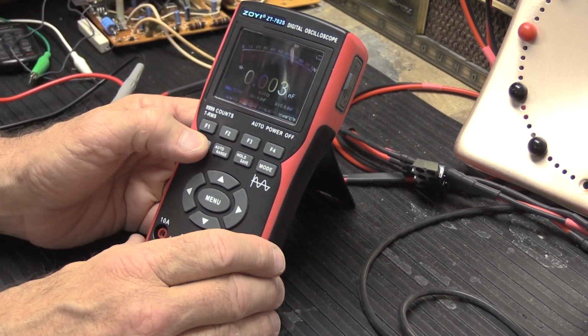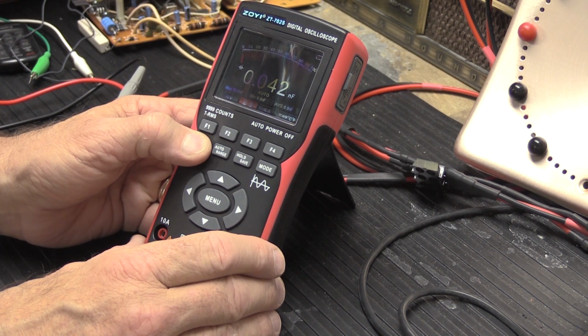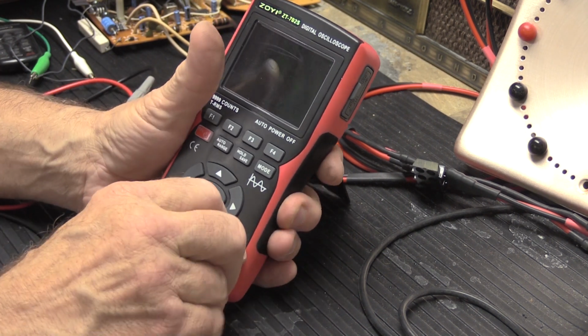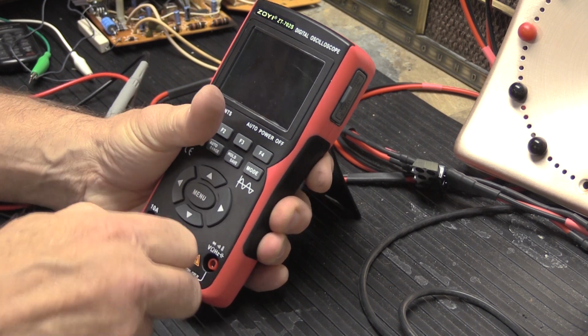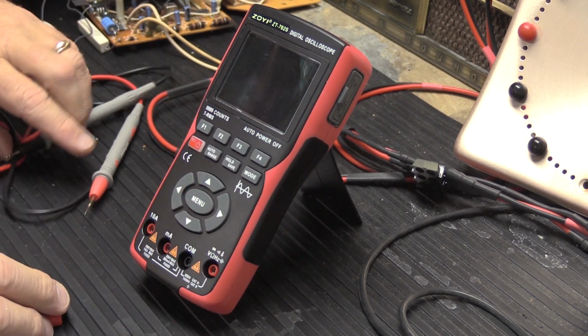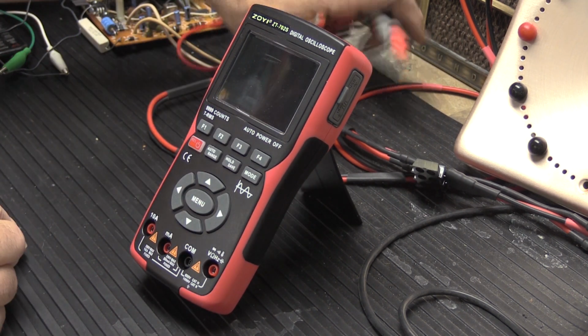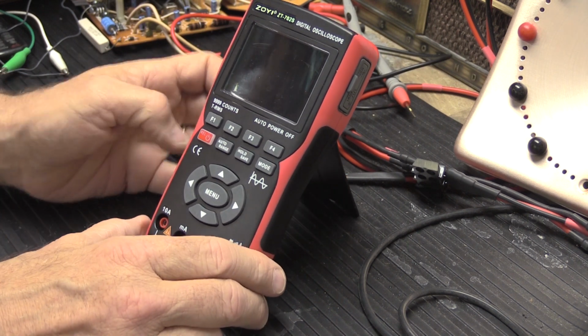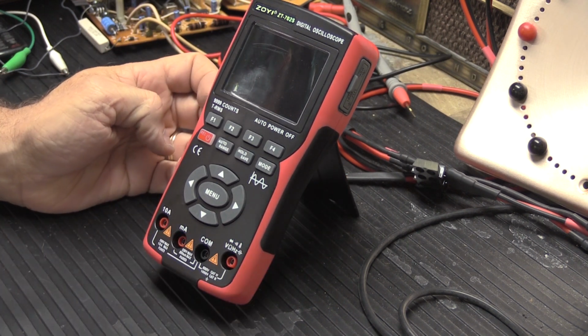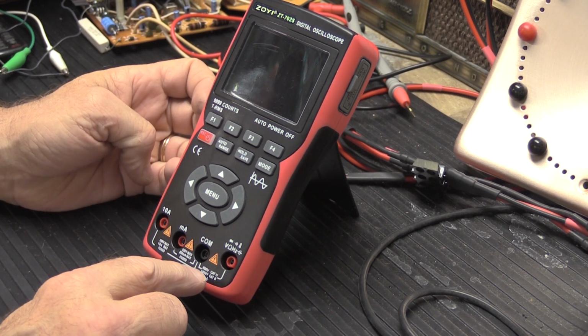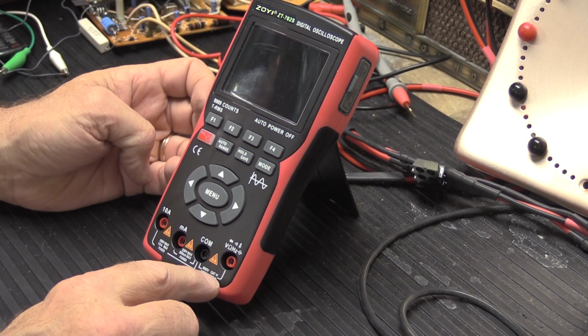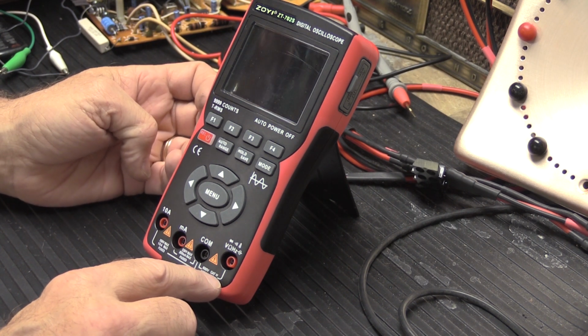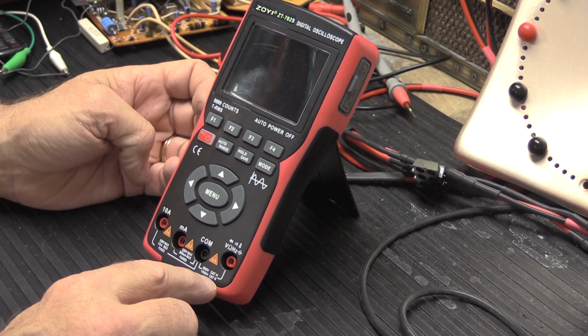Now, I'm going to turn this off now because the battery's getting really low. All right, so meters, or I should say multimeters, have safety ratings. Now this one says it's rated at 600 volts in a Cat 4 rating and 1000 volts in a Cat 2 rating.